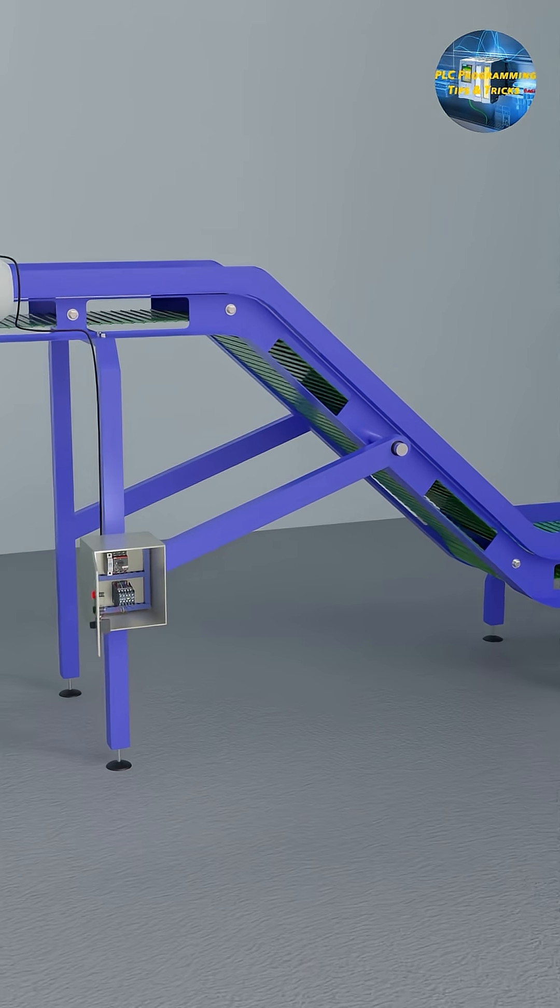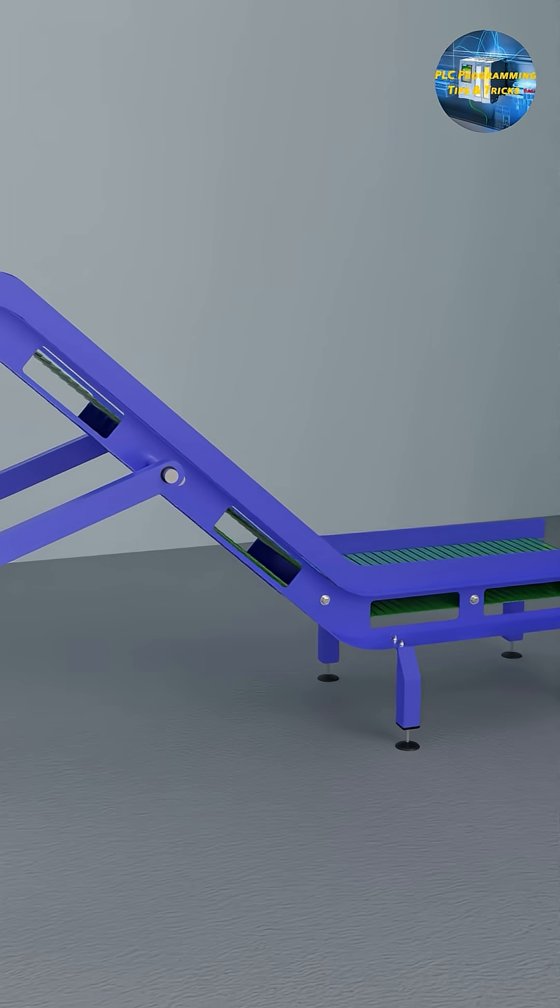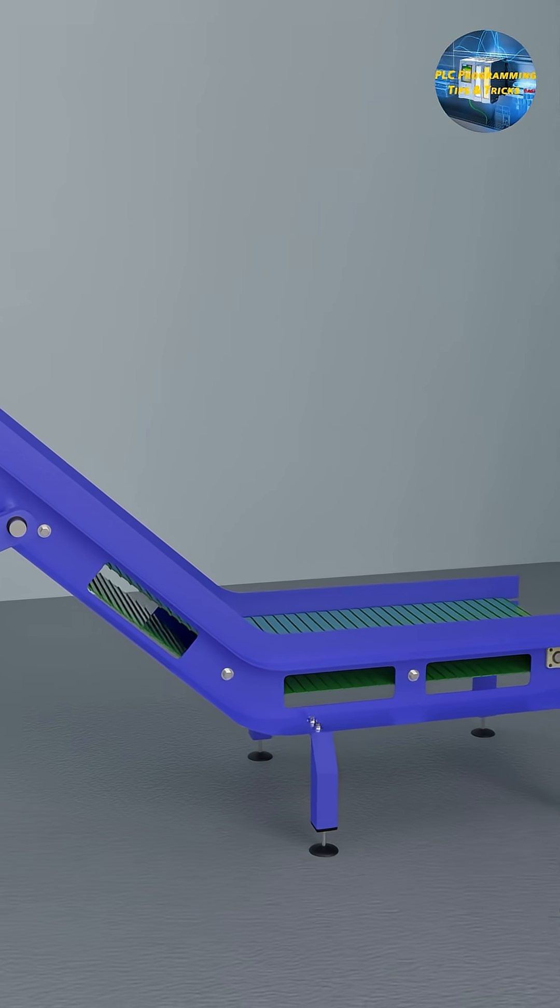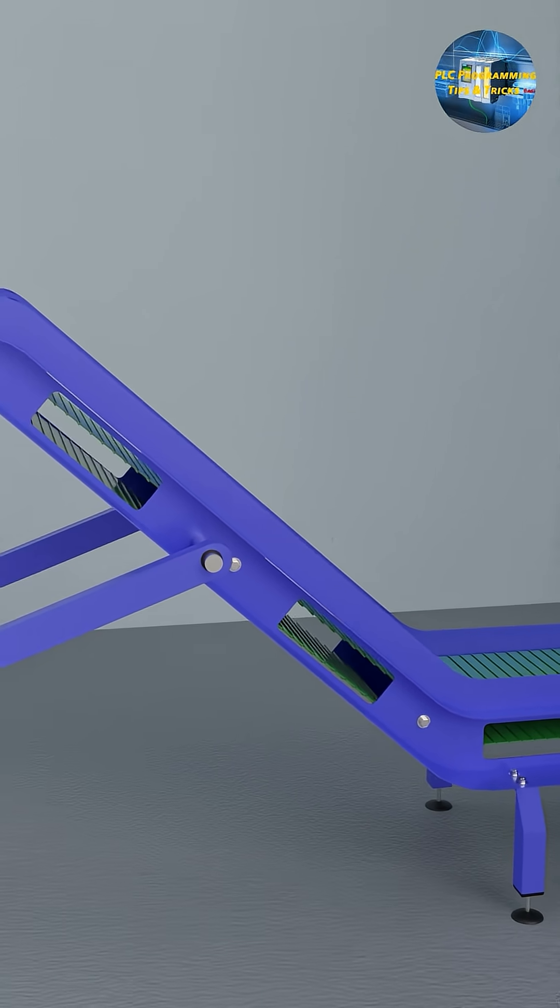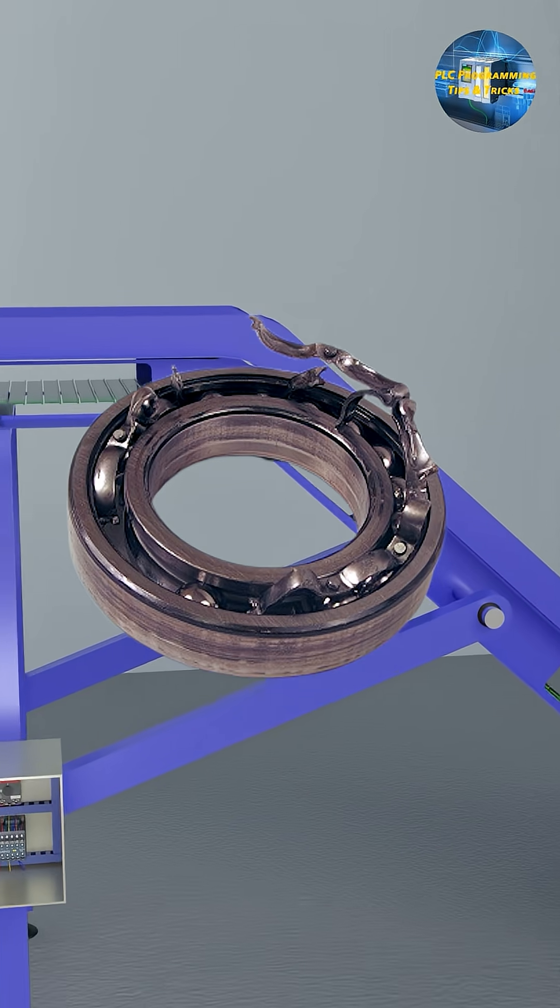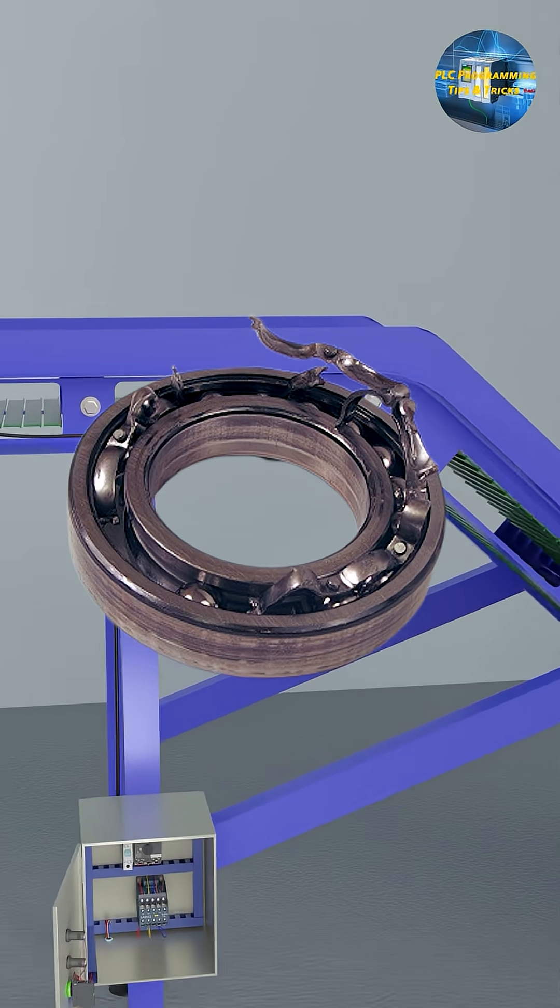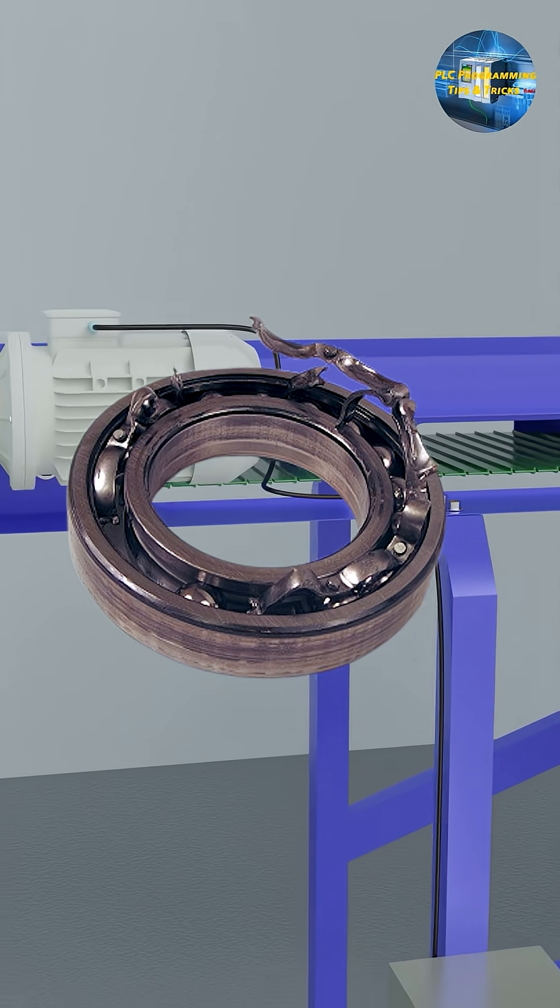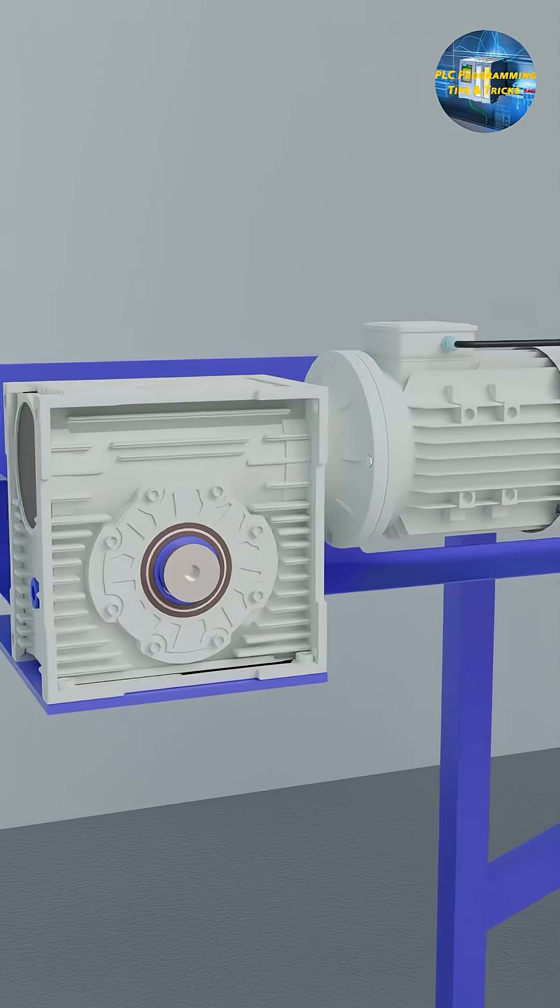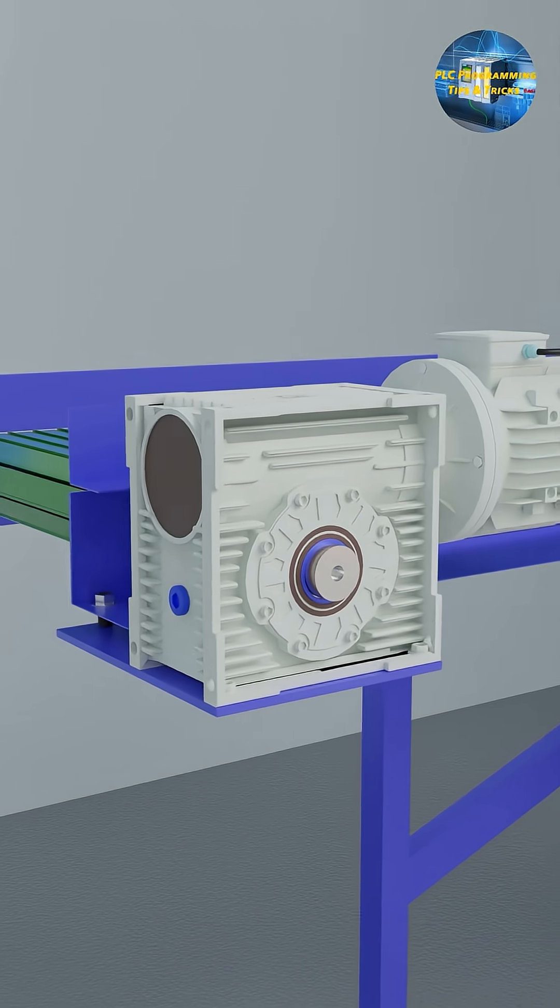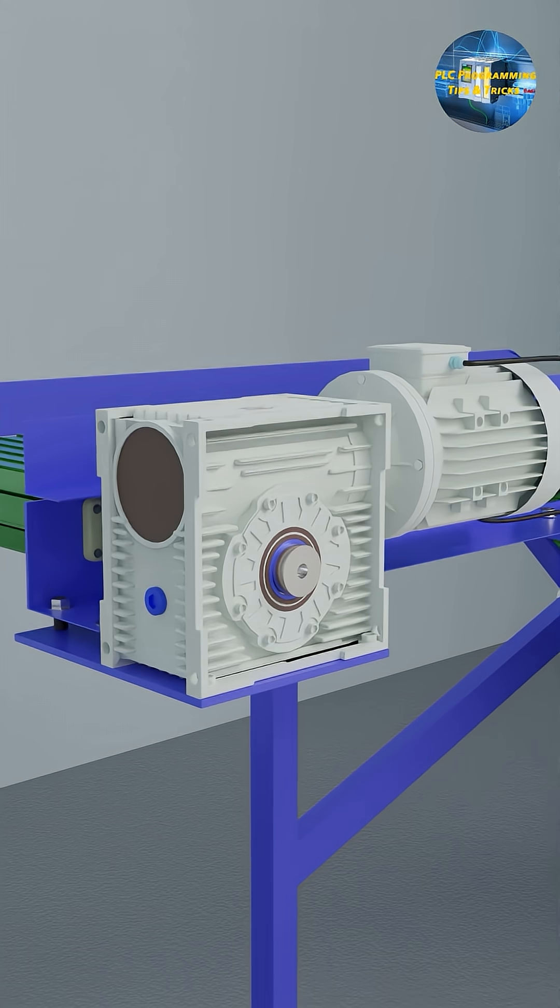So first of all, we will observe the whole conveyor system. Sometimes, something stuck inside the conveyor belt or broken bearings in the system can cause the motor to get overloaded and cause the tripping of the breaker.